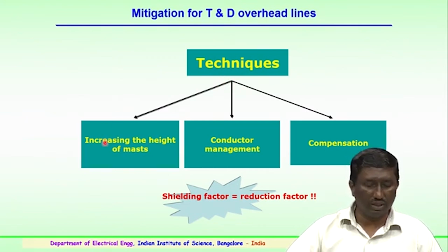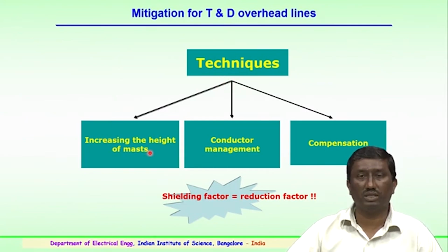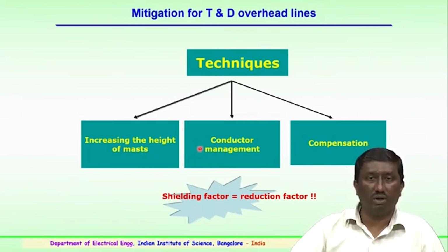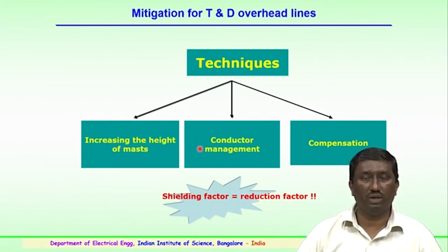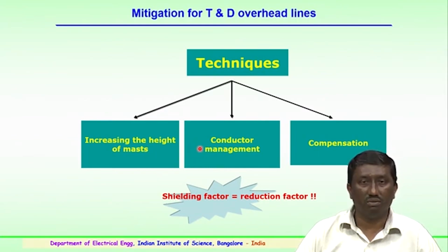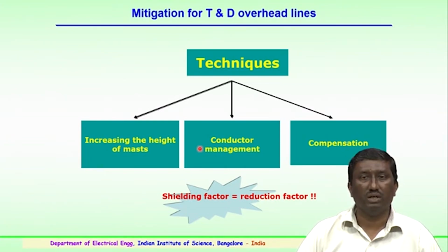So, one of the techniques is to increase the height of the mast. Height of the mast is the tower mast, where it is increased, and the clearances are more. So, with the clearances the electric field in kV per meter comes down, and also the magnetic fields will get reduced on the people who are working on the earth ground level.